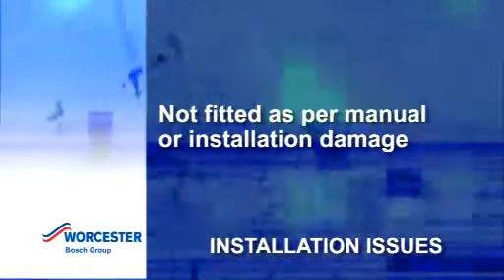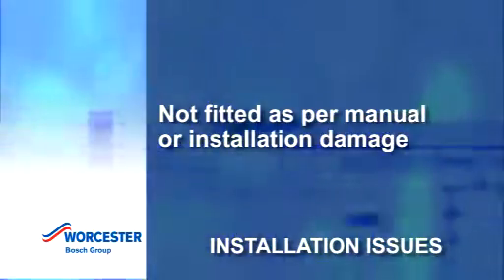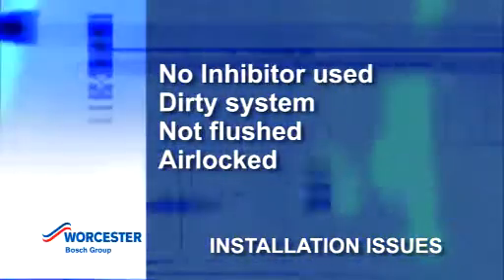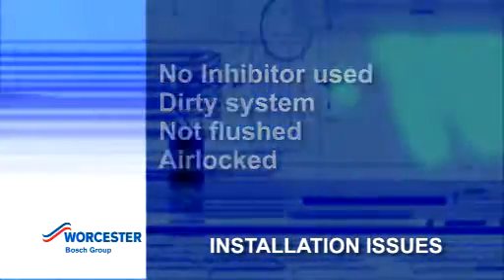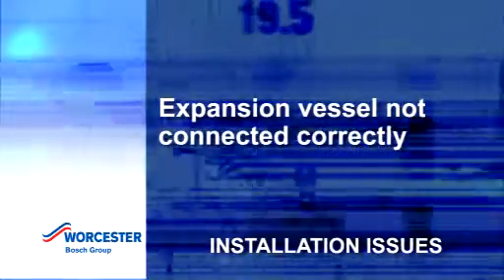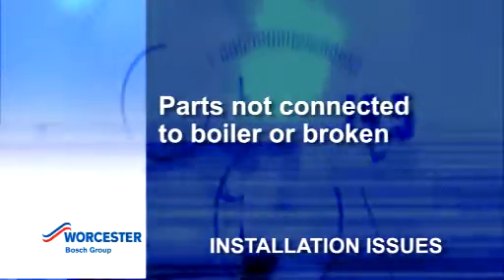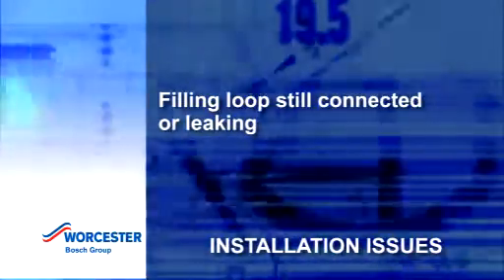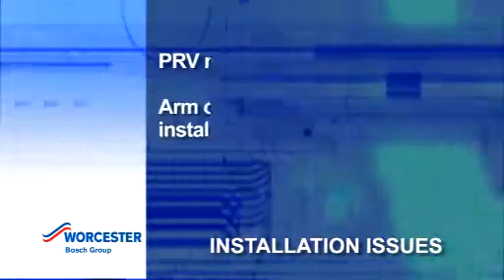Other common faults reported are that the boiler hasn't been fitted as per manual, that no inhibitor has been used, or there's a dirty system, or the system hasn't been flushed, or that the system is airlocked. The expansion vessel has not been connected correctly, thermostatic radiator valves fitted have not been done to standard, or there is a system fault. A part's not connected to the boiler, or that they're broken. The filling loop left still connected or leaking. The pressure relief valve not terminating correctly.